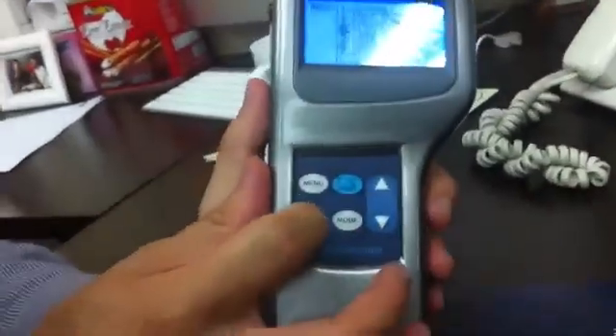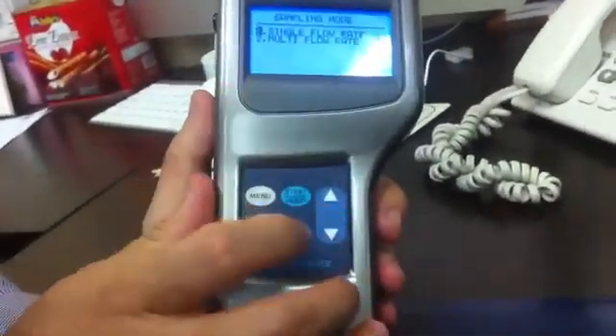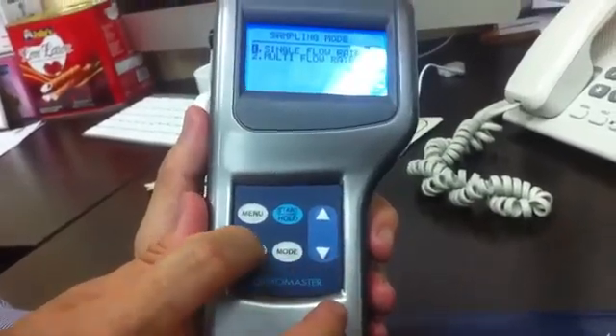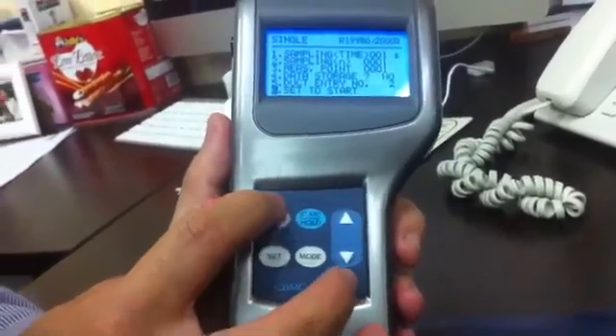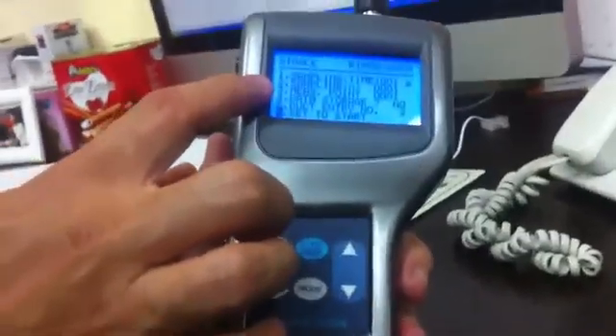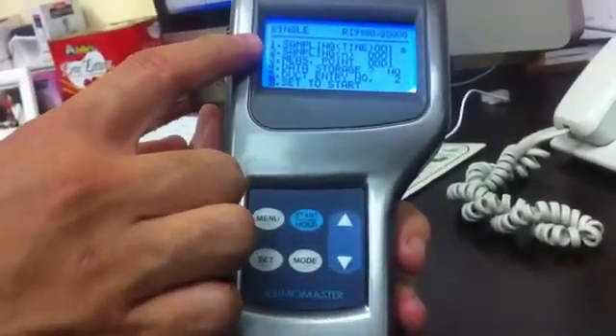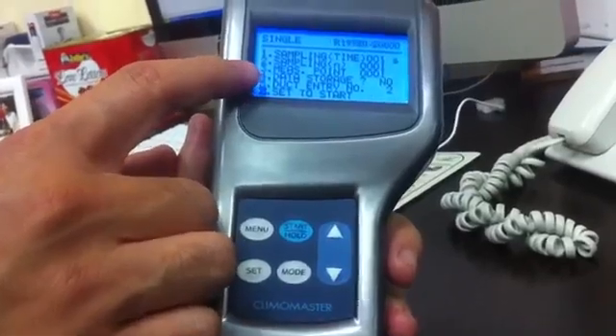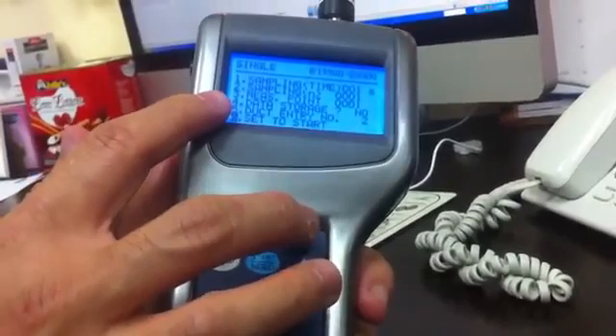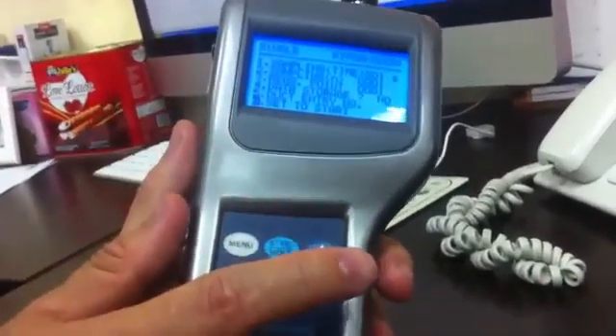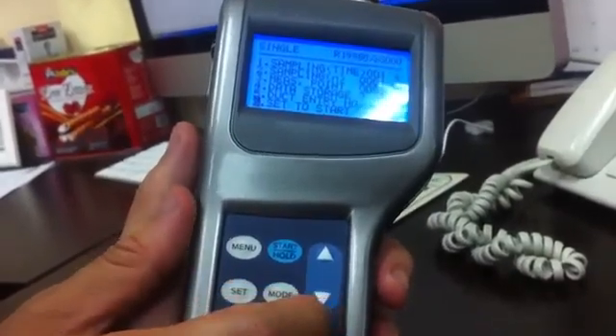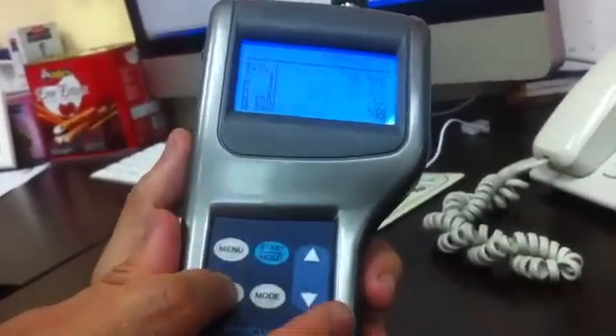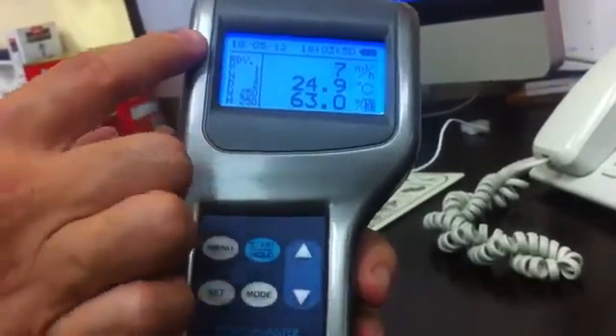If I want the instrument to measure the flow rate, I can do it in single flow rate or multi-flow rate. If I go into single flow rate, I can have a sampling time of 1 second, and then how many samples to take, how many measuring points I want to store the data, and what is the duct entry. In this case, the duct entry is duct number 2, which is a square duct of 250 by 250. If I press enter to start, it's ready.